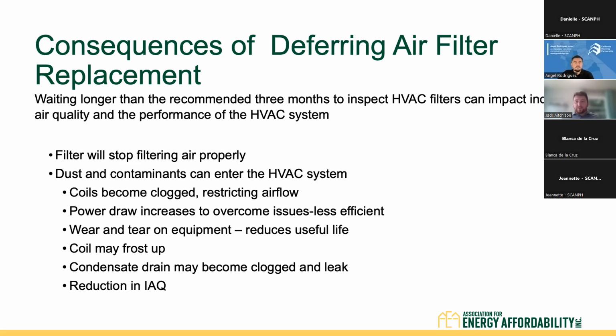Essentially, you have a fan in there. If that fan has to work harder than what it's designed to pull air through that filter because it's clogged, that fan is going to burn out faster. So wear and tear on equipment is going to reduce the useful life. The coil may frost up. When you're in cooling mode, that coil is going to have really cold refrigerant, and it needs to draw energy out of the air in order to avoid freezing. If it's not getting enough airflow because that filter is clogged, it's going to frost up. And then a condensate drain may be clogged and start to leak. You're also going to have a reduction in indoor air quality. If you are not properly filtering the air that is being conditioned, it could cause issues around indoor air quality.